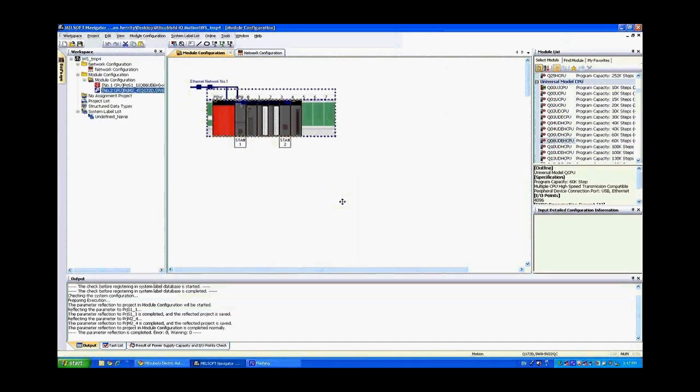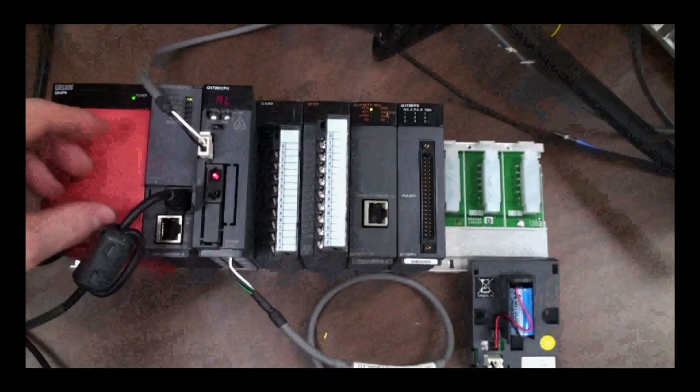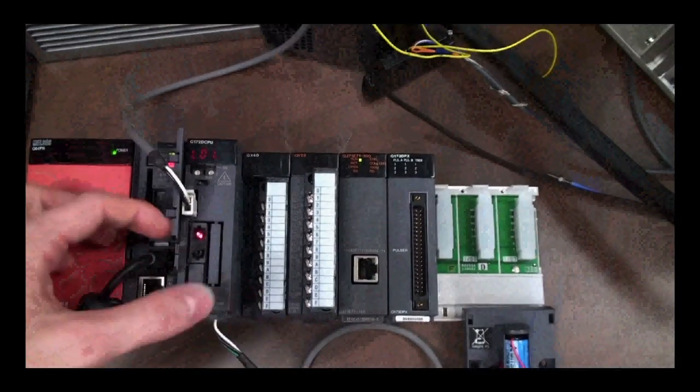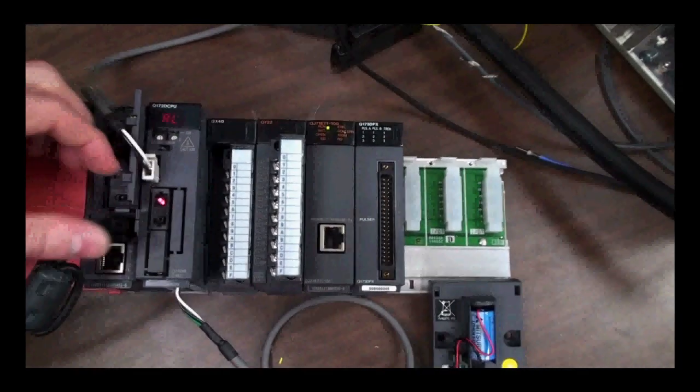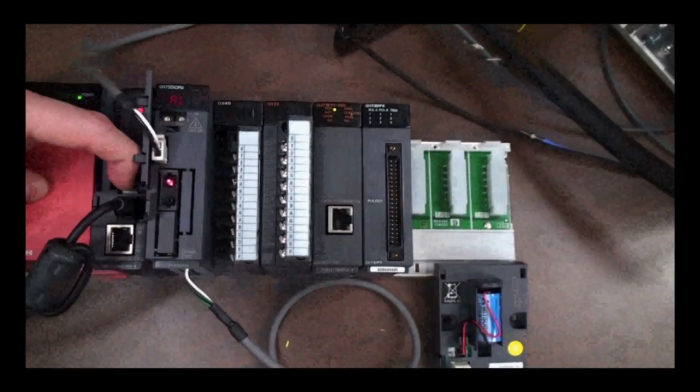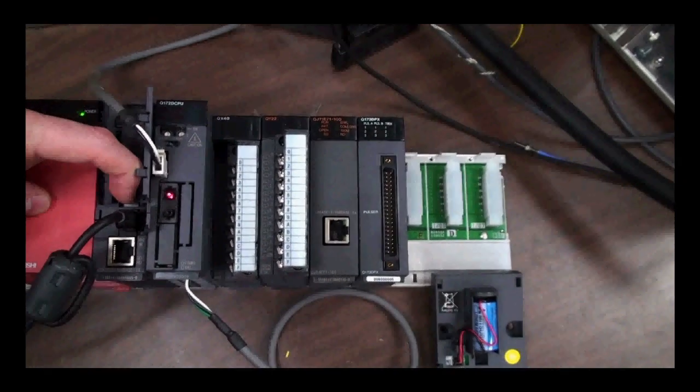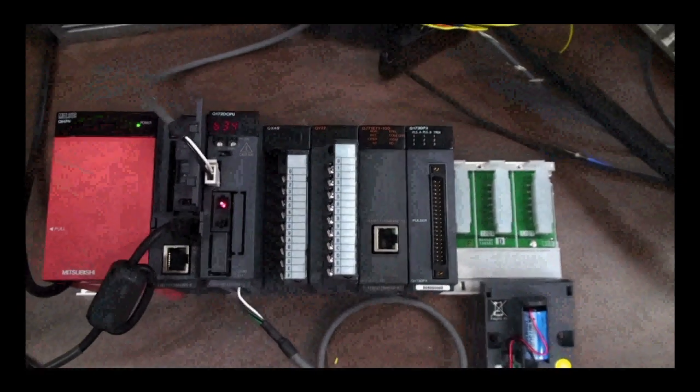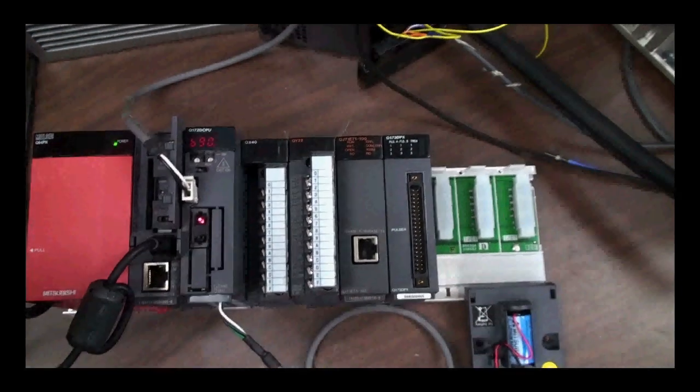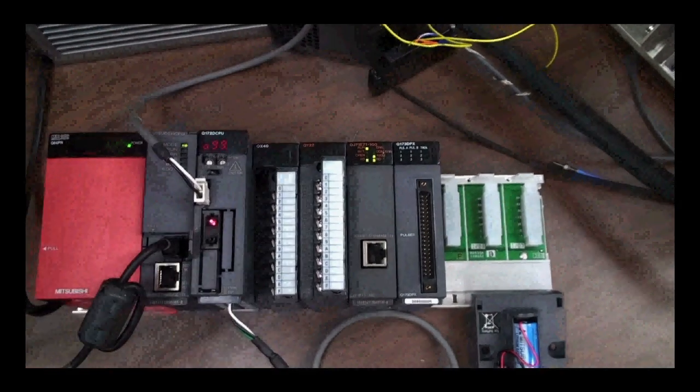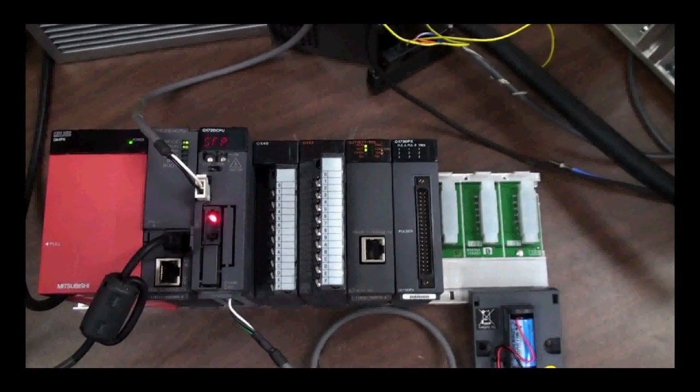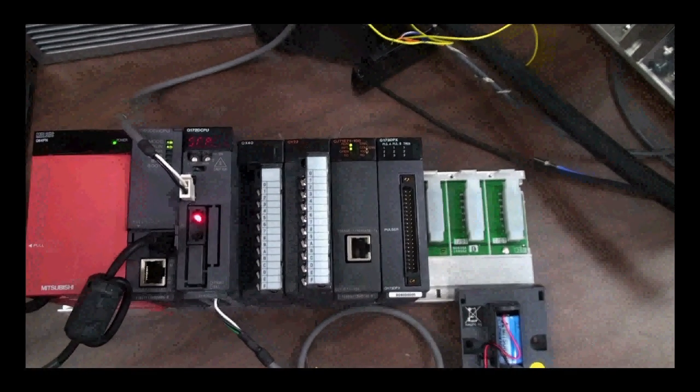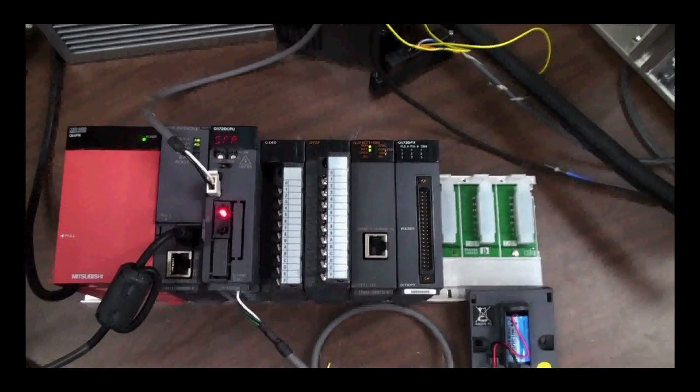Now you should be all set. So with your system you can go ahead and open up the cover on the PLC. And go ahead and hold the switch. The run stop switch. All the way to the left. Hold it there for a second or two. And then it will reboot. And then push it over to the right. It will bring everything back up online. If everything is successful you will not have any errors. The motion controller goes into stop. And you see there is all green LEDs. Everything is ready to go.